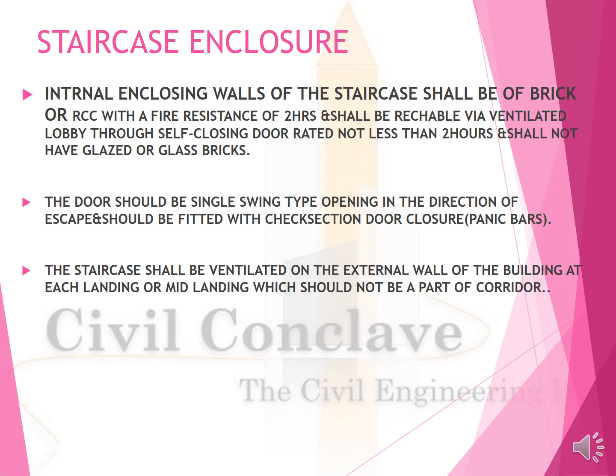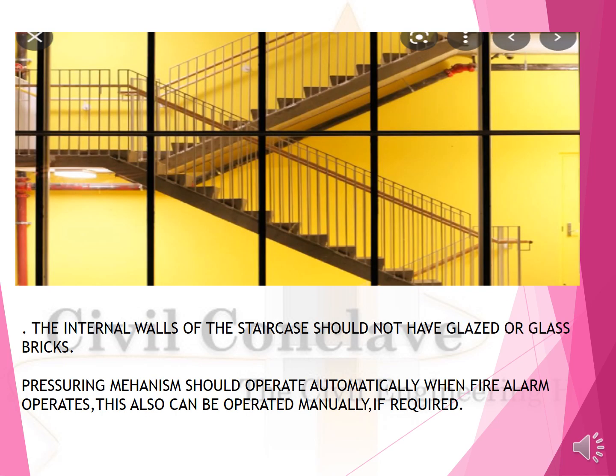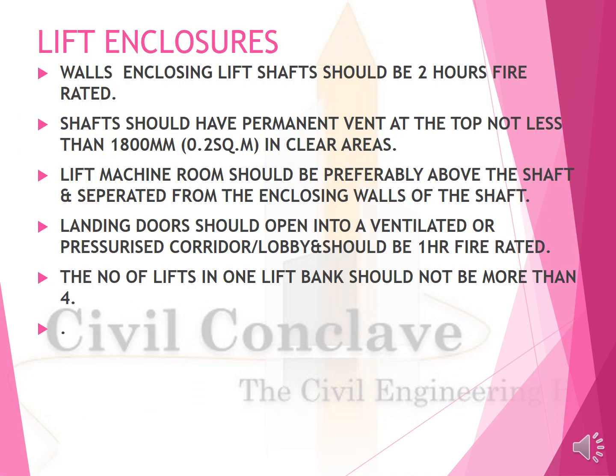Staircase enclosure. Internal enclosing walls of the staircase shall be of brick or RCC with a fire resistance of 2 hours. The door should be a single swing type opening in the direction of the escape. The staircase shall be ventilated on the external wall of the building at each landing or mid landing, which should not be a part of the corridor. The internal walls of the staircase should not have glazing or glass bricks. The pressurizing mechanism should operate automatically when the fire alarm system operates. This can also be operated manually.